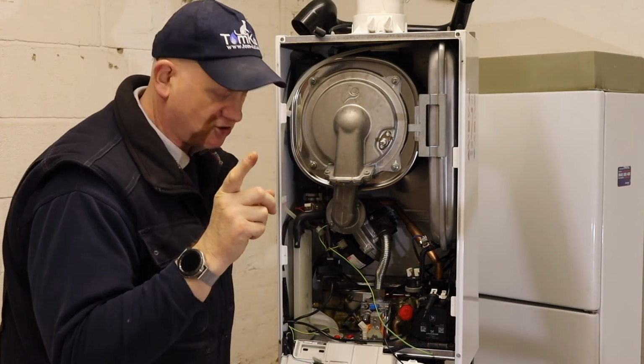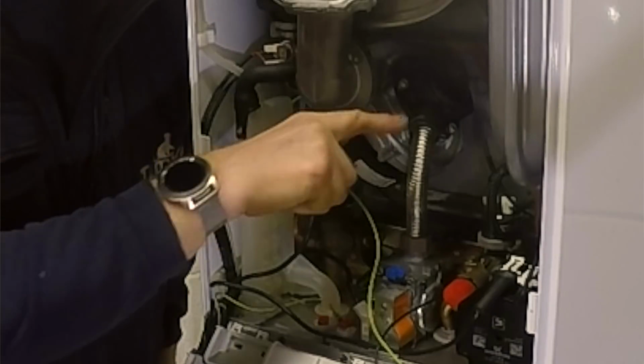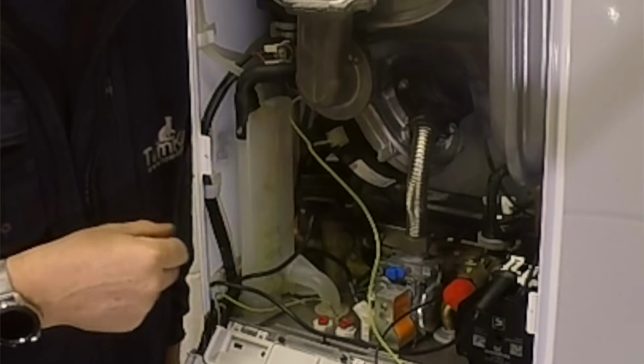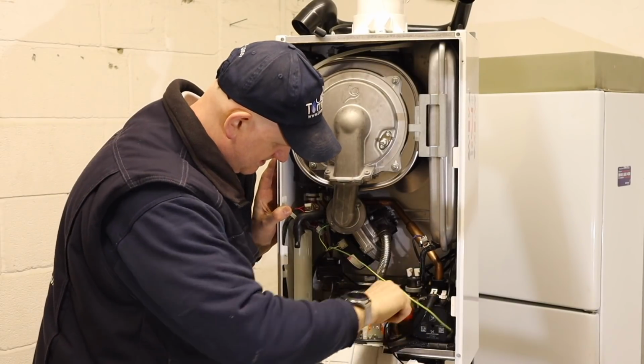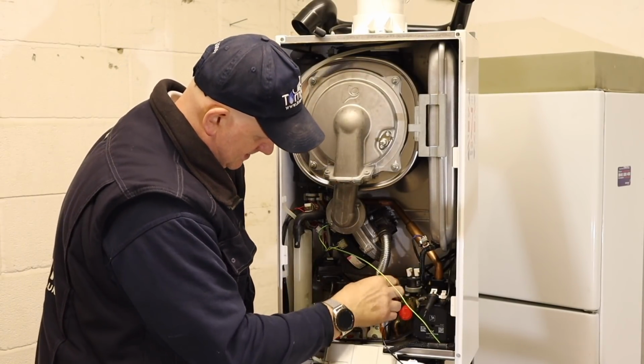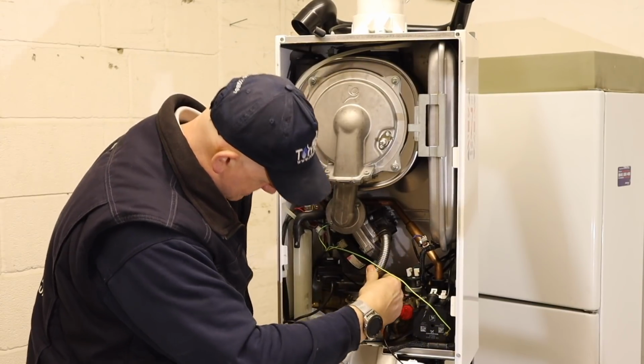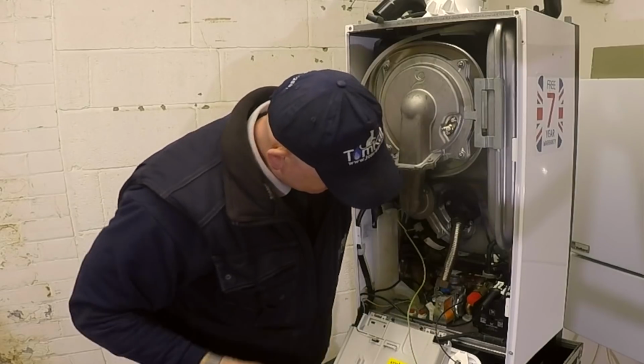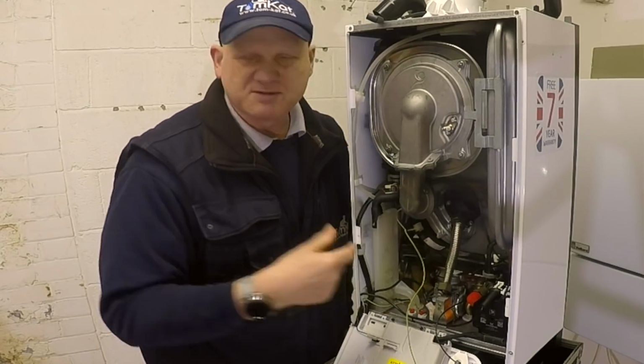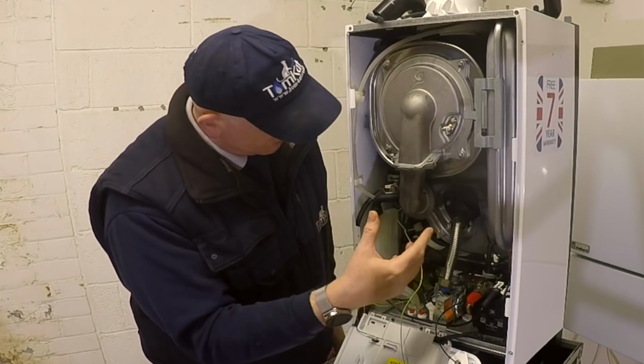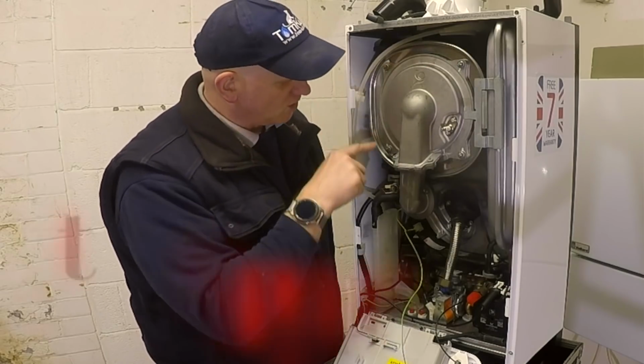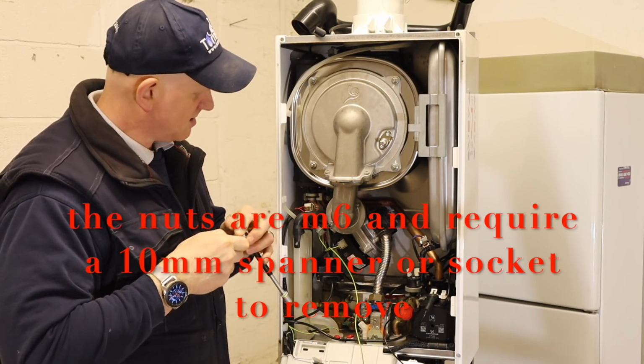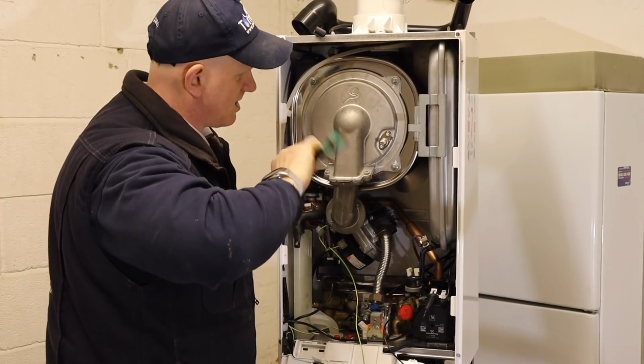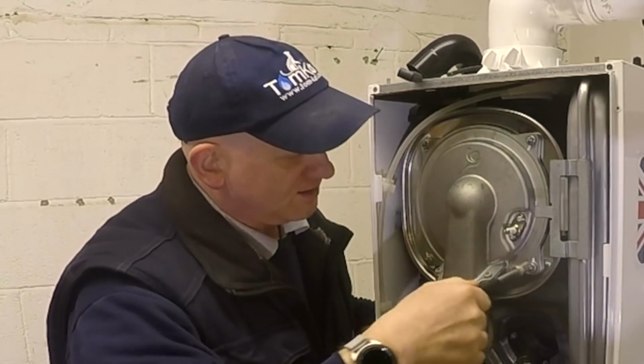So next we've got the gas connection. Now there are two ways of undoing the gas connection. There's one there where you can just pull the pin out and that should slide out. Or the easiest way is to undo the nut here. So if I get my adjustable spanner, and there should be an O-ring in there which is missing. So make sure you don't lose that. Remember, this is a demonstration boiler. So that's now undone. All we've got to do now is undo these four 10mm nuts. So if I get them out of the socket, I'll just slacken them off. That's 1, 2.